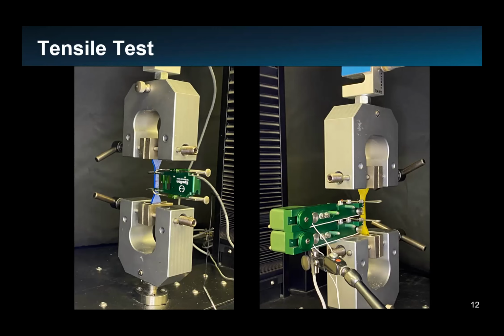With the universal testing machine, we can perform compression tests and tensile tests. A tensile test is a type of mechanical test that measures the tensile strength and other mechanical properties of materials. During the test, the specimen is held between two grips, as you can see in the pictures, and the machine applies a force to the specimen in a vertical direction. This force is applied gradually, and the resulting deformation of the specimen is measured by a displacement sensor. In this case, for example, in the pictures, you can see two different extensometers. So I'm going to talk about the two different extensometers that we can use on tensile tests.